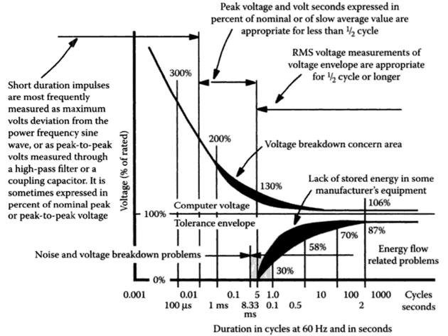Ideally, AC voltage is supplied by a utility as sinusoidal, having an amplitude and frequency given by national standards in the case of mains, or system specifications in the case of a power feed not directly attached to the mains, with an impedance of 0 ohms at all frequencies. Topic: Power quality deviations. No real-life power source is ideal and generally can deviate in at least the following ways.